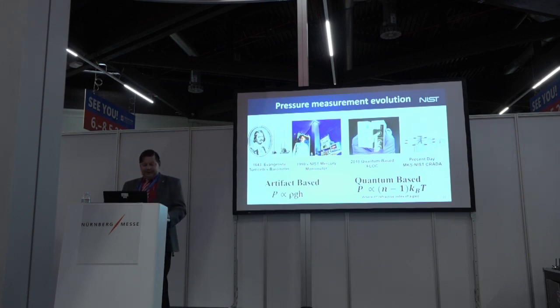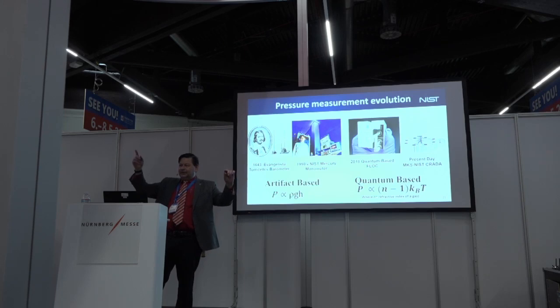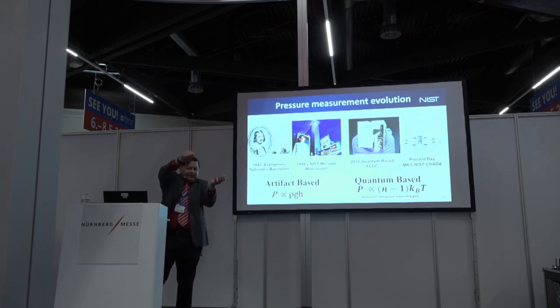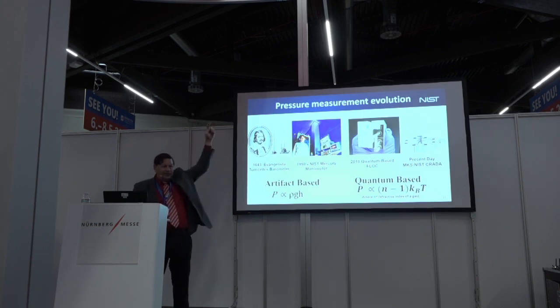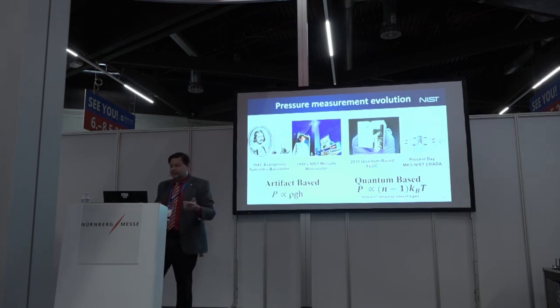In terms of the timeline of how we got to where we are with mercury barometers and pressure measurements, what you're seeing up there is Evangelista Torricelli in 1643 inventing a mercury barometer. He's playing with mercury and a glass tube. He has a bowl of mercury and a glass tube. He seals one end of the tube so it's like a cup, and he fills that tube all the way to the top with mercury. He puts his thumb over the top and places it underneath the surface of the bowl of mercury, releases his thumb, and then holds this 1 meter long glass tube. He notices that when he makes that glass tube more than 1 meter high, there's this little gap that appears at the top. It doesn't matter how long he makes the tube, it's always the exact same height between the bowl of mercury and the gap. As we now know, that gap is called a vacuum, so he not only invents a barometer for measuring pressure, he also invents the concept of vacuum, getting rid of all the gas in a system to create a pressure-free zone.